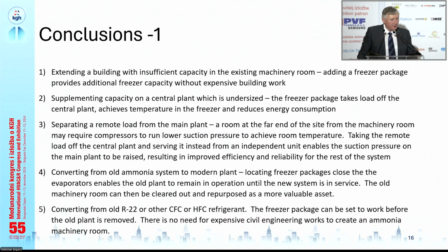So some conclusions. Firstly, extending a building with insufficient capacity can be done without disrupting the plant at all. So the concern that people have that they're not able to cope with the complexity or with the downtime, it doesn't matter. It's not relevant. Adding capacity to an undersized plant, the new plant will take load off the old plant and will achieve the temperature in the freezer and reduce the energy consumption.